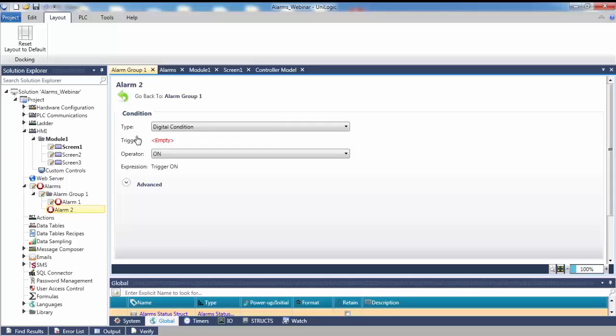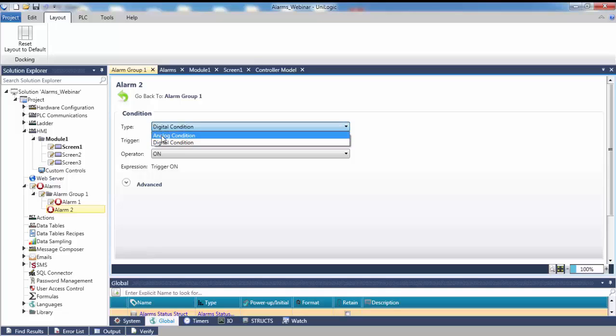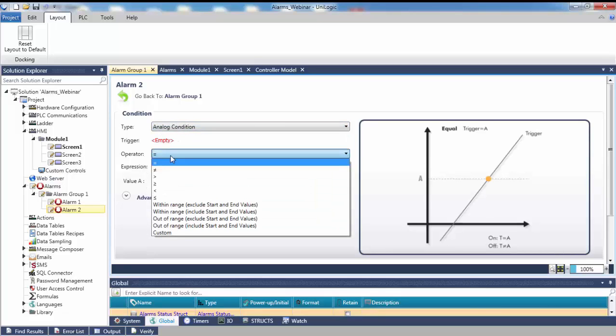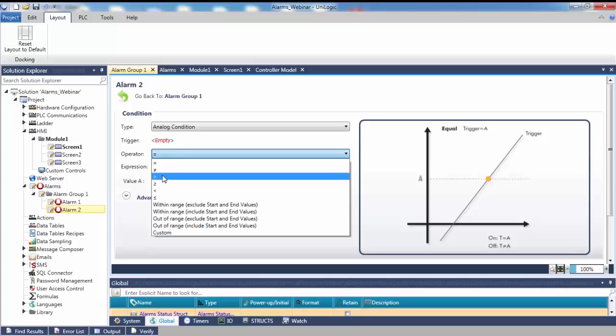Because this alarm is based on a range of values, set the condition type to be analog. Analog alarms can be configured for greater than, less than, equals to, not equals to, or within or out of a range. In this example, the trigger of the alarm will be the temperature exceeding an upper limit of 200 degrees. Select the greater than operator.